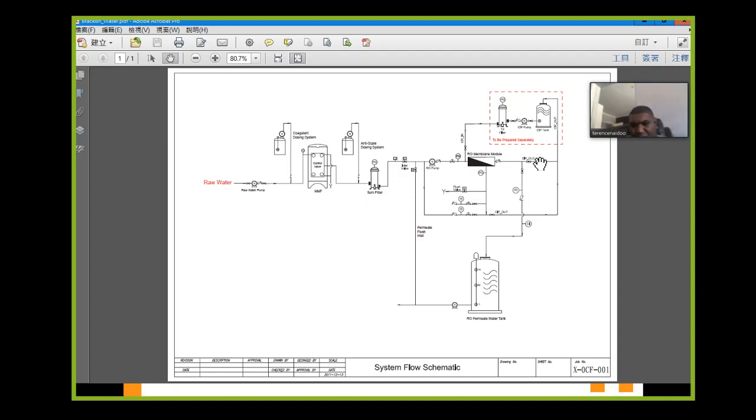Why do we need to do that? Because sodium chloride can eat up metal components when the system stands by. When the system is running, it's okay, because water keeps running. It doesn't have the time to eat up. It can still eat up the carbon compounds from the metal components, but very slowly. But when the system stands by, then it eats up very quickly. So the corrosion usually happens when the water is sitting on metal components for a long period of time.